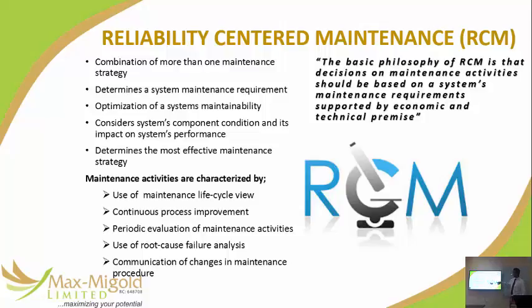Now, the thing that makes it a little bit more complex is the fact that you have to do root cause analysis for every failure and have that root cause analysis documented for every failure. So you have to ask yourself whys, 5 whys for example, using fishbone or any of those other analyses, because basically you must document why it failed. Reliability requires that you change strategy to reflect a correction on that failure, the reason for that failure.